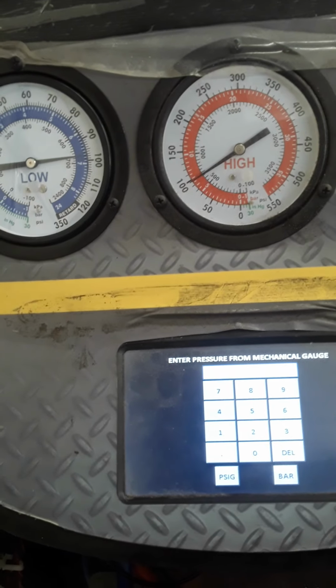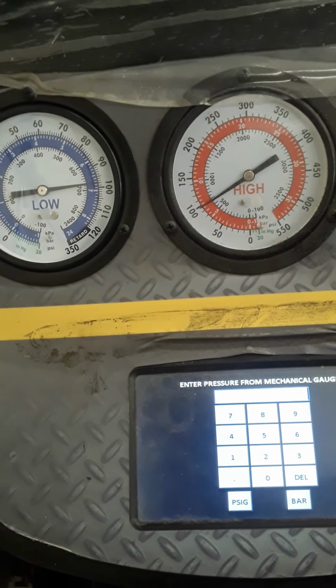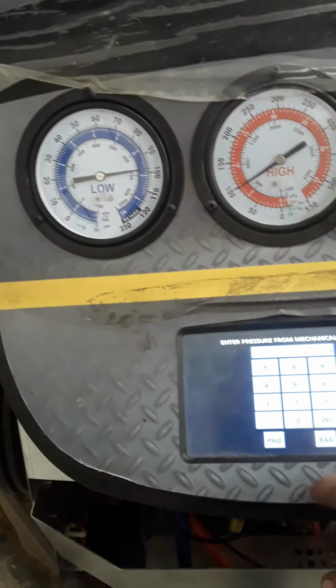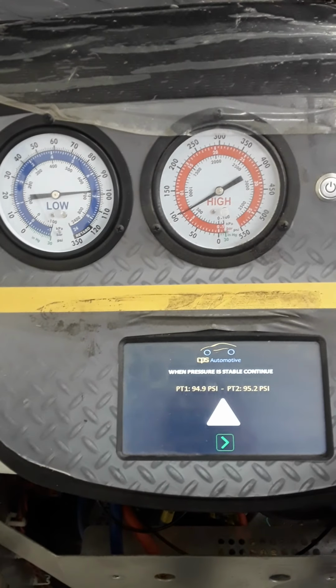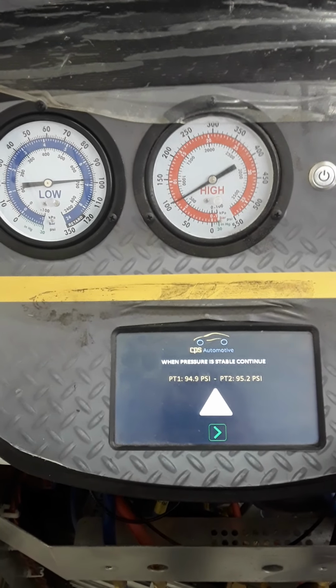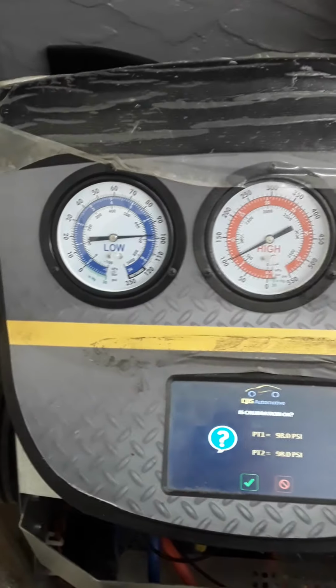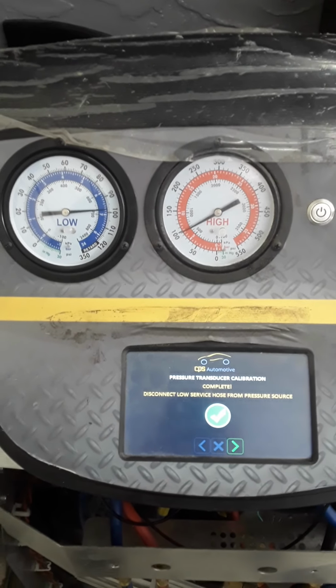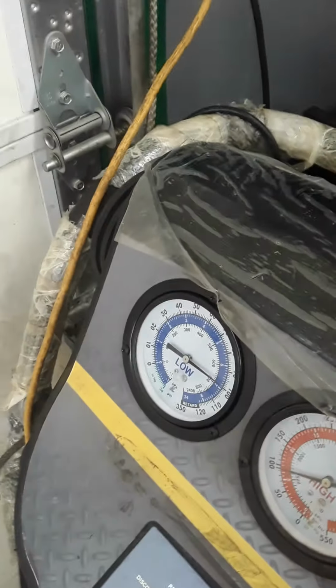But realistically, we should be able to calibrate around that even without doing it, unless it's really way off. You have a 9/16 wrench? I do. You got a 9/16 wrench, just break the low side blue hose, the low side manifold hose, up underneath the bottom going up into the machine. Break it loose right there and see if that gauge goes to dead 0. Right. I've already moved past that, trying to shoot this quick little video for you guys.